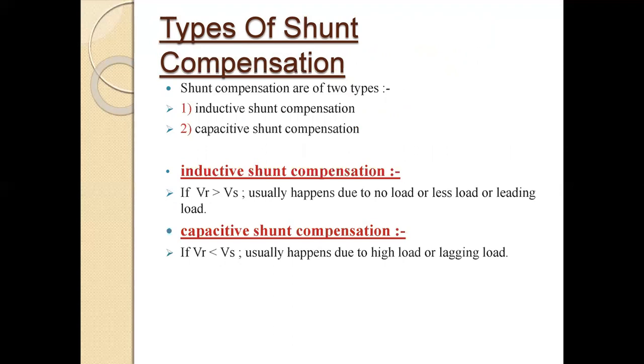In inductive shunt compensation, VR is greater than VS, meaning the receiving end voltage is greater than the sending end voltage, which usually happens due to no load, less load, or leading load. And second, capacitive shunt compensation. If VR is less than VS, meaning the receiving end voltage is less than the sending end voltage, this usually happens due to higher load or lagging load.